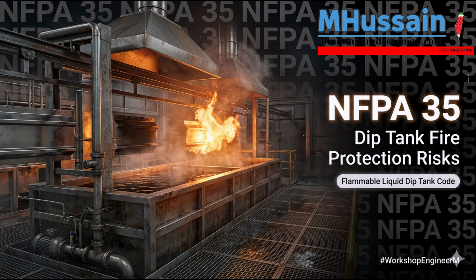Right. Completely different. Such requirements demand that inside storage rooms for nitrocellulose be physically separated from production areas by 2-hour fire-rated walls. But the most critical element is the fire suppression system. That deluge. Yeah. The room must be protected by an automatic sprinkler system, preferably a high-speed deluge system, capable of delivering an incredibly dense water application rate, 0.35 gallons per minute per square foot over the entire storage area. That is a lot of water. To put that math in perspective, 0.35 gallons per minute per square foot is a torrential, hurricane-level downpour.